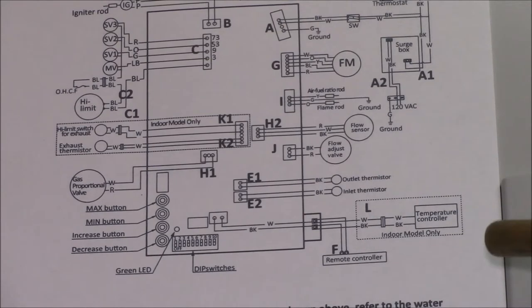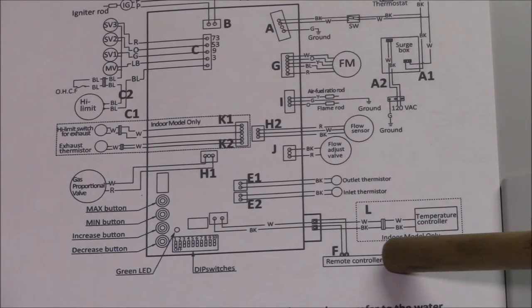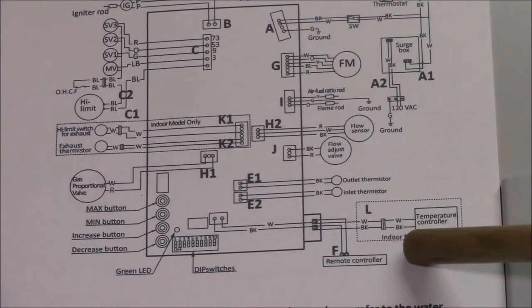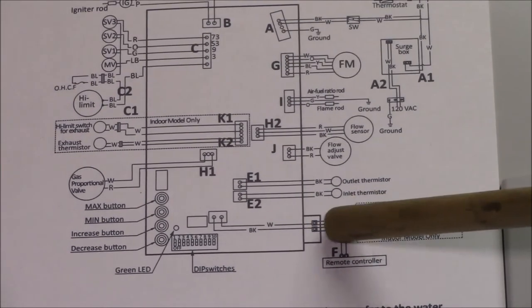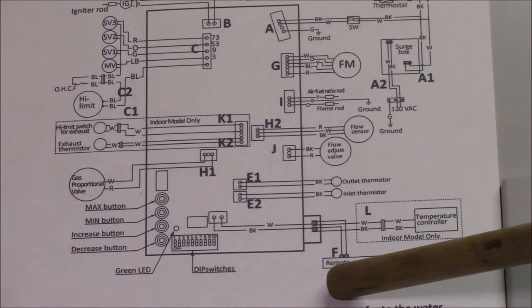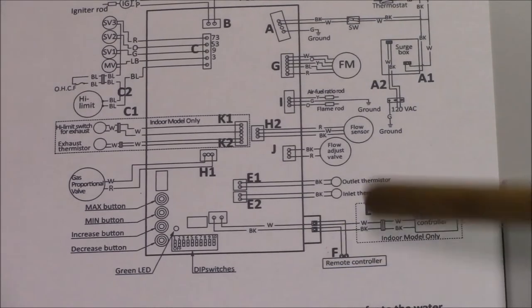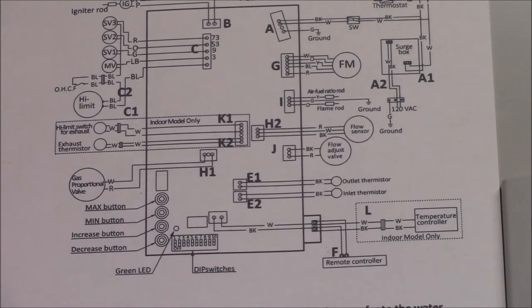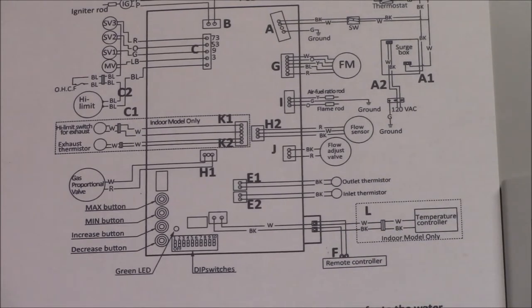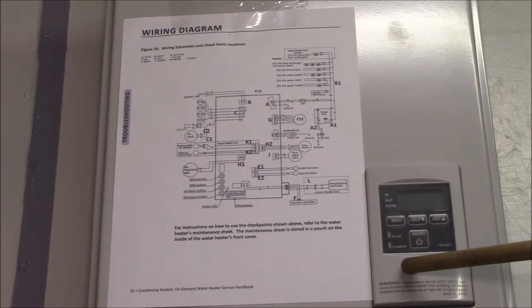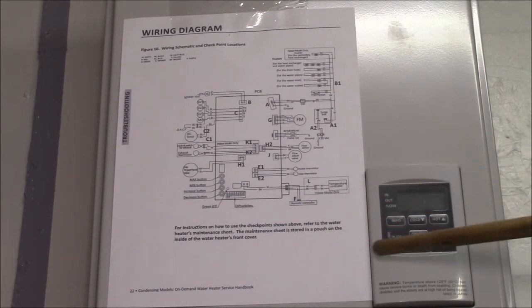This is the wiring diagram out of the service manual that you can download from the Takagi website. Right here it says indoor model only temperature controller - there's two wires, a connector and two wires that go over to a little terminal block. The remote controller wires up to those same two terminal connections, so the built-in or front panel remote is wired in parallel with the actual remote. That says that this remote is basically the same as the official remote.